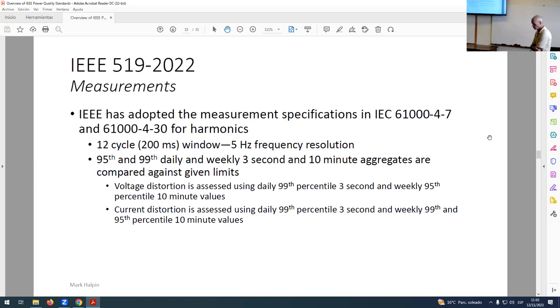In the 2014 edition, and I was the chair of the 2014 version of 519, we introduced the measurement protocols from IEC 61000-4-7. Before 2014, we had harmonic limits, but we didn't have any standardized way to measure. Wait a minute. How can I require you to keep your harmonic current at or below a certain number and not specify how that number is going to be measured? You can't do that. But we did. We did it that way for 30 years. Right? But in 2014, we stopped that.